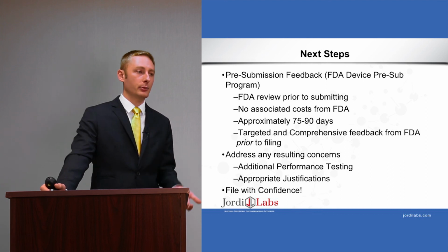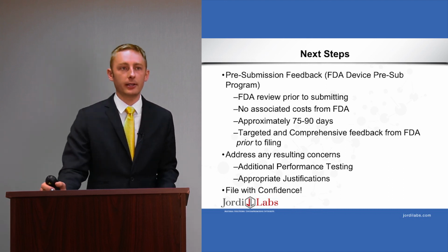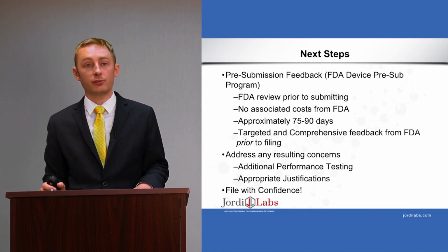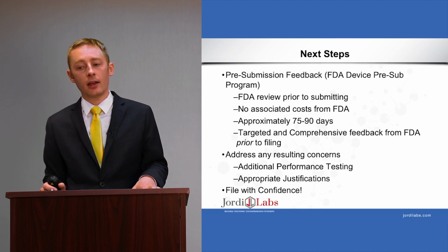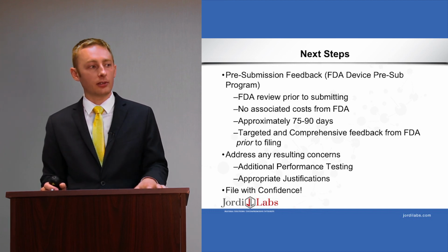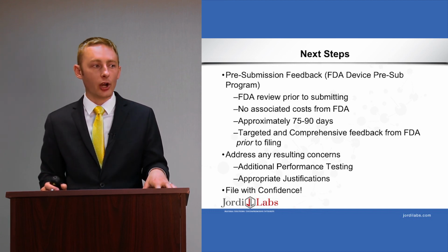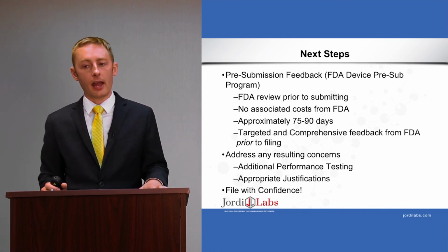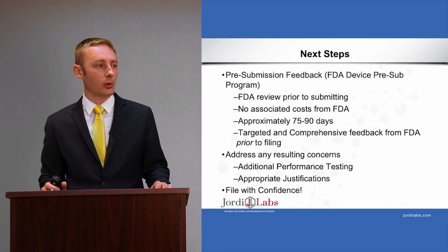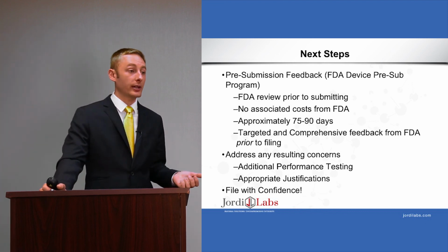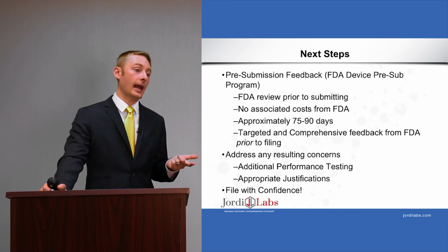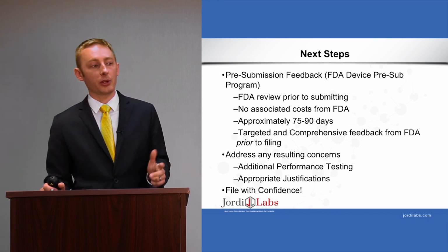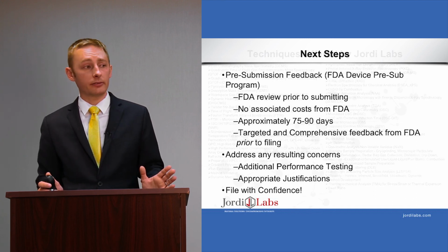It does add between 75 and 90 days, but in most cases, our clients have been very happy with going through the pre-submission feedback process because it helps identify where the FDA may have concerns, and then we can get targeted and comprehensive feedback from the FDA before we file and have any sort of filing deadlines imposed on us. It gives you time to address any resulting concerns, address any additional performance testing, hopefully none needed, and then also provide appropriate justifications. And with that, you can file with confidence.